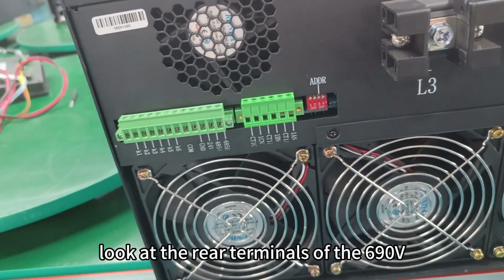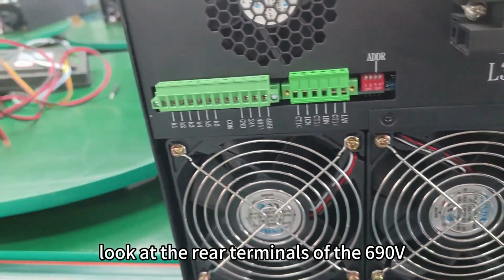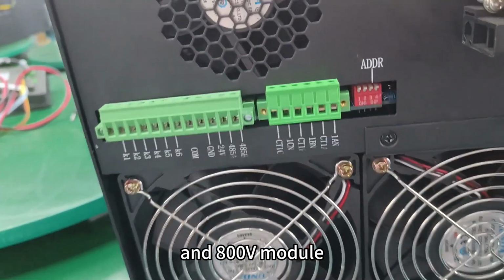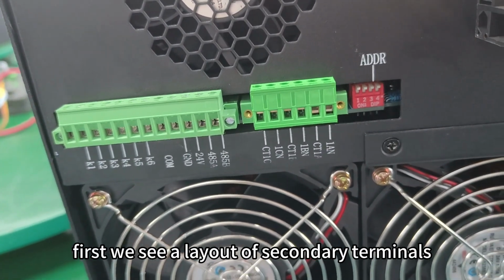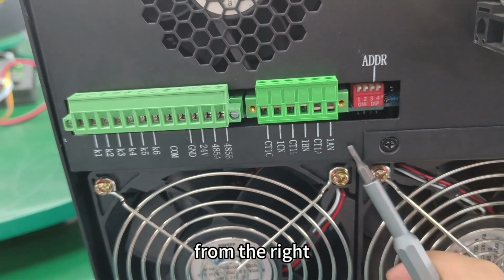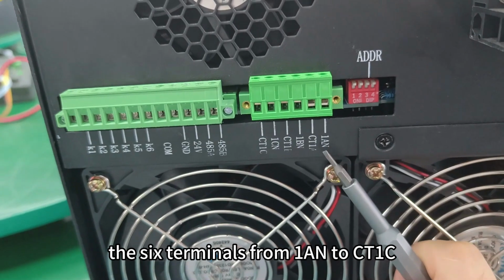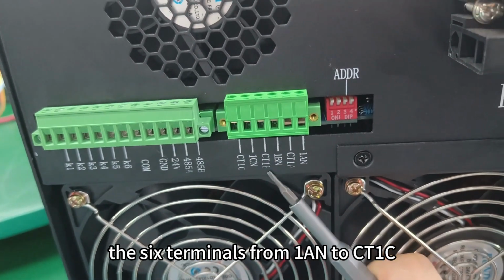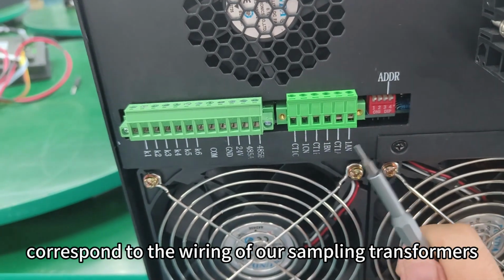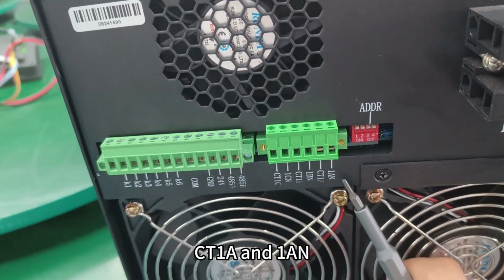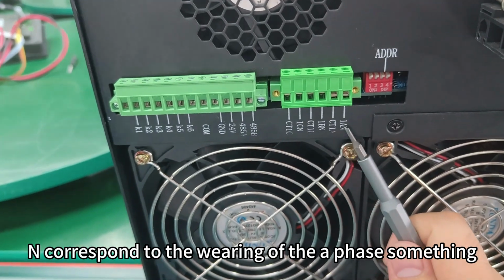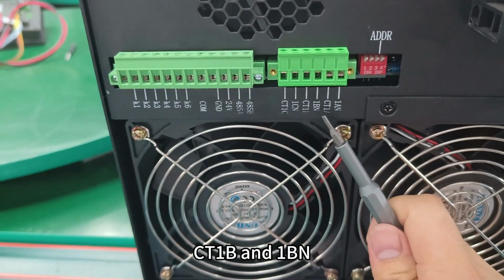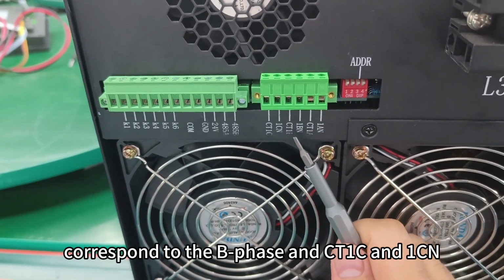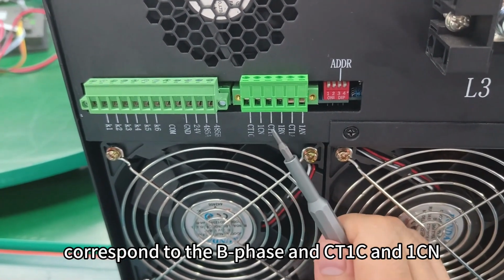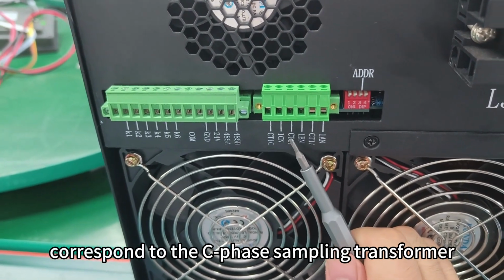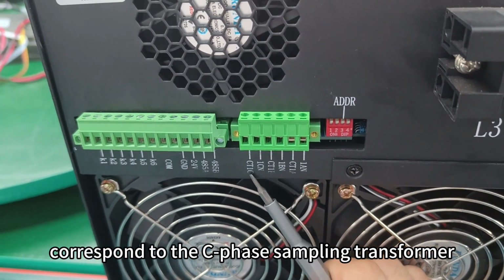Next, let's look at the rear terminals of the 690 volts and 800 volts module. First, we see the layout of secondary terminals. From the right, the 6 terminals from 1AN to CT1C correspond to the wiring of our sampling transformers. CT1A and 1AN correspond to the wiring of the A-phase sampling transformer. CT1B and 1BN correspond to the B-phase, and CT1C and 1CN correspond to the C-phase sampling transformer.